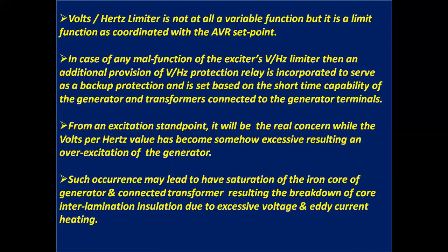From an excitation standpoint, it will be the real concern while the volts per Hertz value has become somehow excessive, resulting in overexcitation of the generator. Such occurrence may lead to have saturation of the iron core of generator and connected transformer, resulting the breakdown of core interlamination insulation due to excessive voltage and eddy current heating.